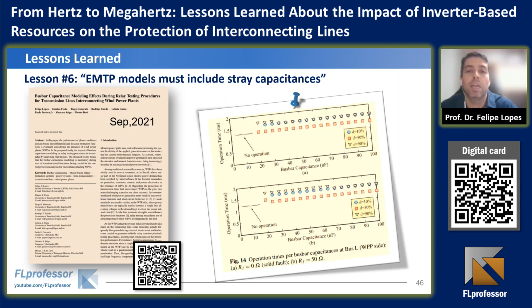So in this paper, we demonstrated that including the stray capacitance in simulations would not affect phasor-based functions, which were available in relays 1, 2, and 3 here for distance functions. But for traveling wave functions, it was a mandatory modeling strategy, because if you disregard the stray capacitances, you will conclude that traveling wave-based functions will not operate in that system. And this is, at least in my opinion, an erroneous conclusion. It depends on the system, so you have to analyze the stray capacitance, and perhaps you can use traveling waves in a reliable way.